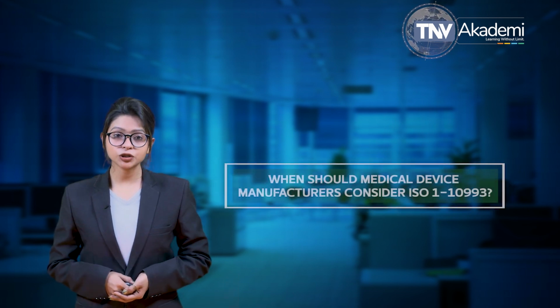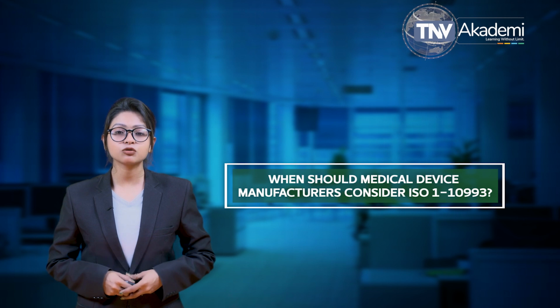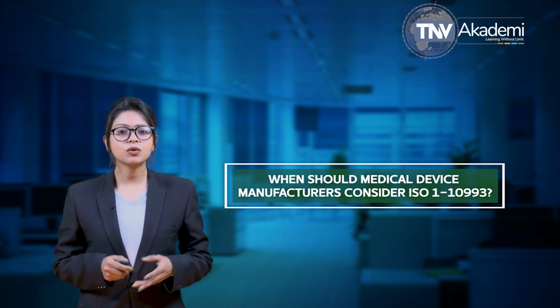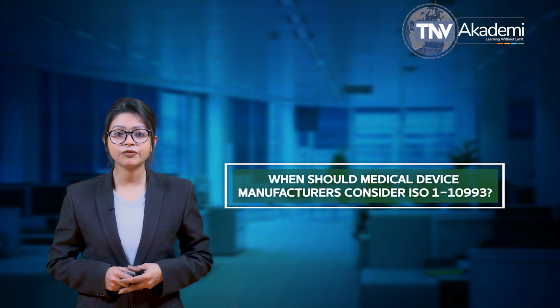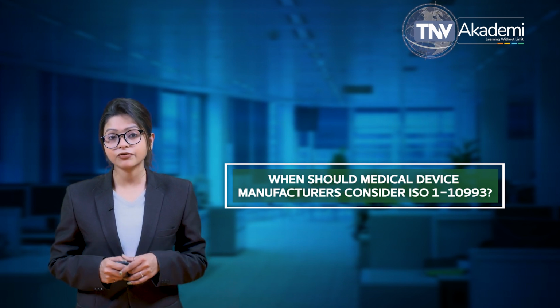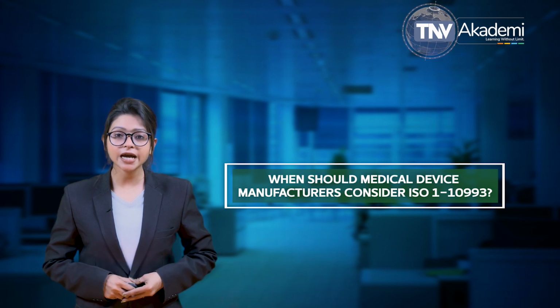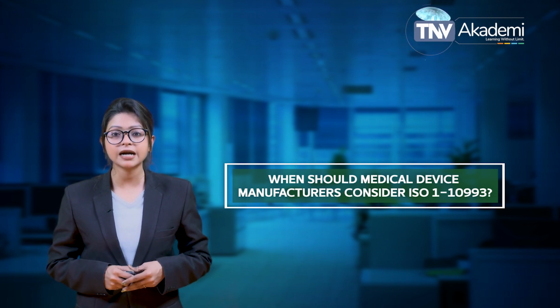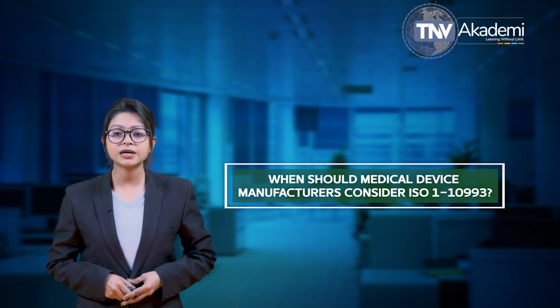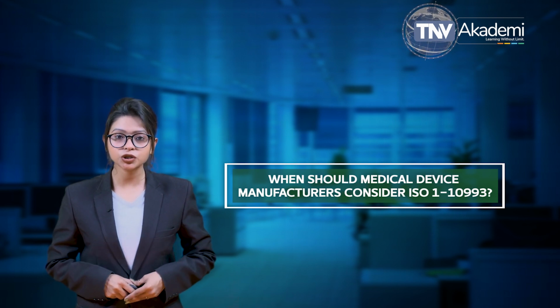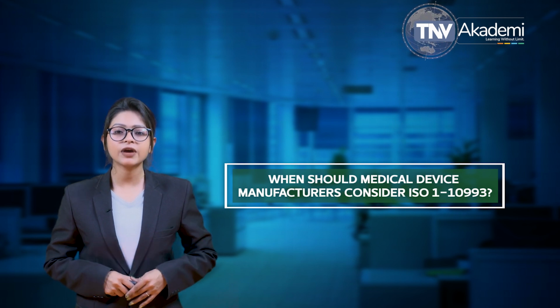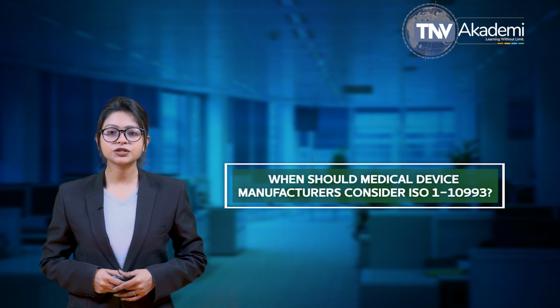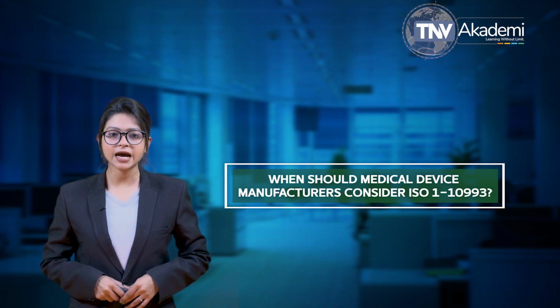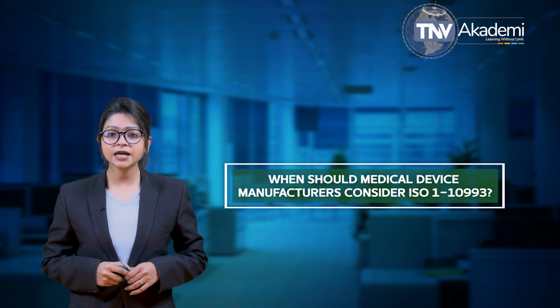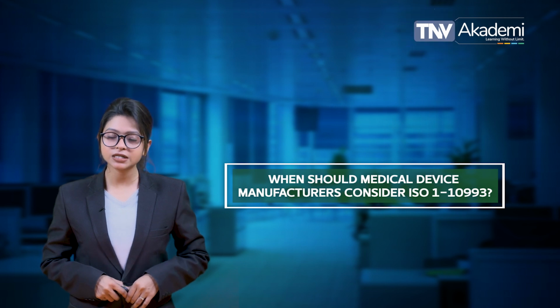So let's talk about when medical device manufacturers should consider ISO 10993-1. ISO 10993-1 is applicable fairly early in the medical device testing and risk management process. This is because it actually helps medical device manufacturers understand their product testing requirements by classifying medical devices according to the nature and duration of the contact with human tissues when in use. So once a manufacturer identifies this information, they can use it as a guide to identify the biological endpoints that need to be addressed to support safety for the device according to the standard.